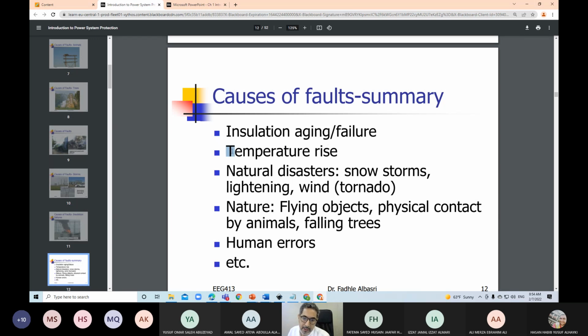And that insulation damage, as you said, is because of temperature rise. I showed you also nature: storms and lightning strikes can also cause faults. Human errors could be, sometimes, a human error in setting a relay so it will not detect a fault, or a human error when he maintained equipment, he lost a spanner or a piece that created a short circuit after the maintenance guy left the site and someone tried to open the switch on the circuit.